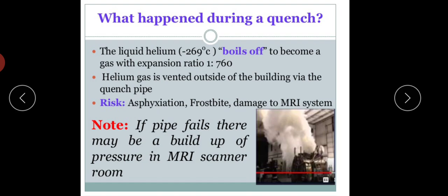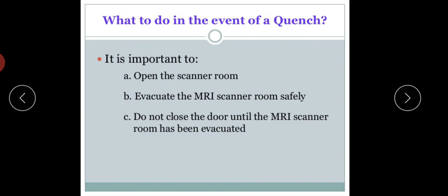What to do in the event of a quench? It is important to open the scanner room and evacuate the MRI scanner room safely. Do not close the door until the MRI scanner room has been fully evacuated.